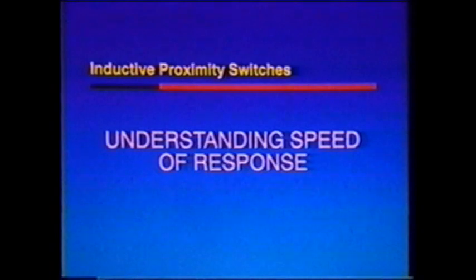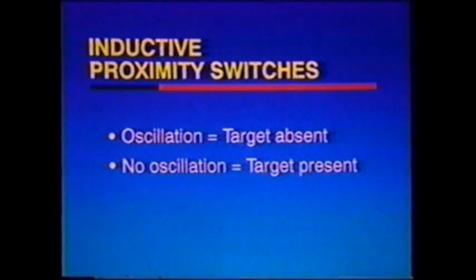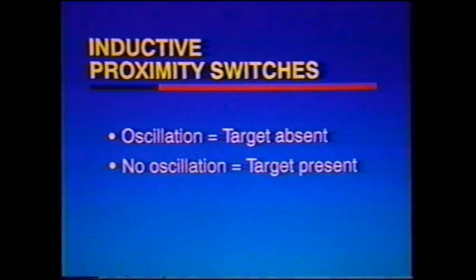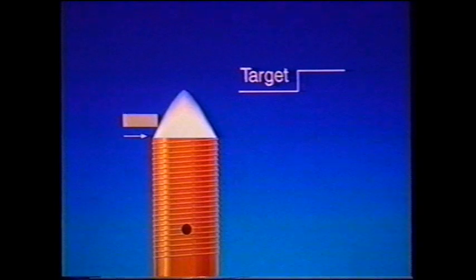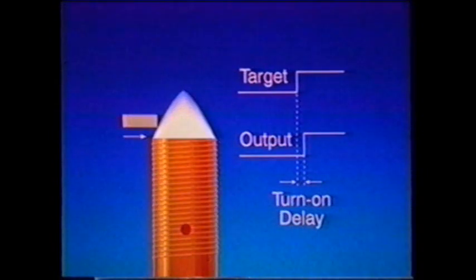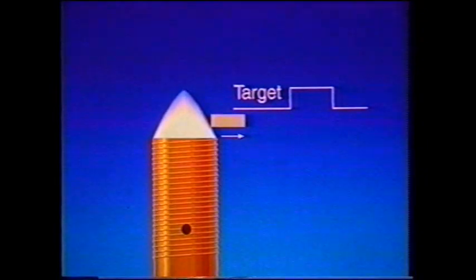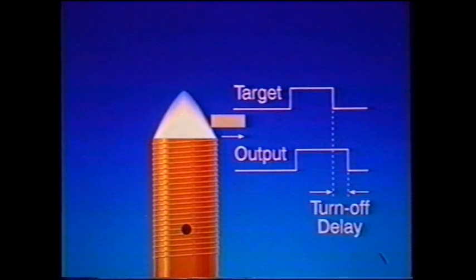Because they are solid state devices, proximity switches operate much faster than mechanical switches. To evaluate response time in a given application, remember that an inductive switch oscillates if the target is absent. When the target is present, oscillation stops. As a target enters the active zone, the output of the oscillator drops towards zero, and a short time later the output stage switches. The time between the target being detected and the change in output is the turn-on delay. As the target leaves the active zone, oscillation begins again, and when the oscillator reaches a predetermined level, the output switches again. This interval is the turn-off delay, and it can typically range from twice to ten times longer than the turn-on delay.